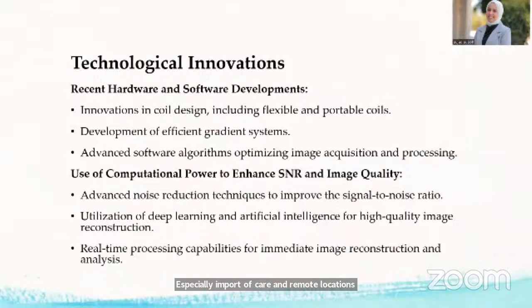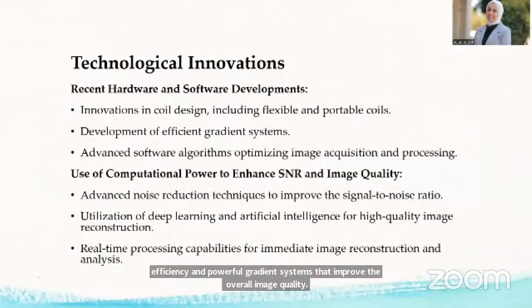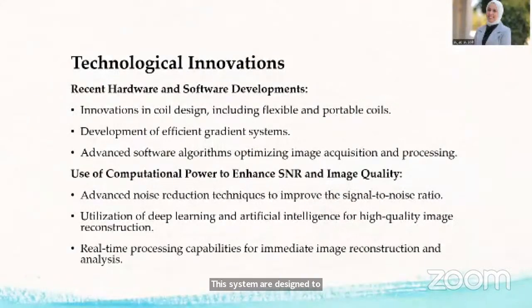Also, there's development of efficient gradient systems, and the gradient system is very important in MRI machines because it's very critical for spatial encoding of the MRI signal. So recent advancements have led to more efficient and powerful gradient systems that improve the overall image quality. These systems are designed to work effectively even at lower magnetic field strength, helping overcome one of the primary limitations of low field MRI, which is the low spatial resolution.